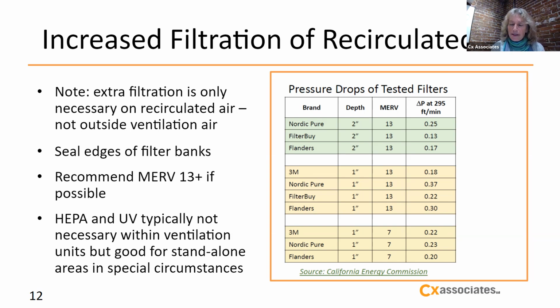The problem with these higher-rated filters is that they have a bigger pressure drop, and your air handling unit might not be able to provide enough air. The fan might not be powerful enough to provide enough airflow. So it's best if your contractor and your designer put these MERV 13 filters in before you do your airflow test. Then you will be able to see how much airflow you are getting in each of the spaces, and how much the air handling unit is able to produce. And then you can decide with your contractor from there: do we need to speed up the fan? Do we need a separate HRV instead, or do we need some portable HEPA filters? Because the air handling unit just can't provide the amount of ventilation that the space requires.